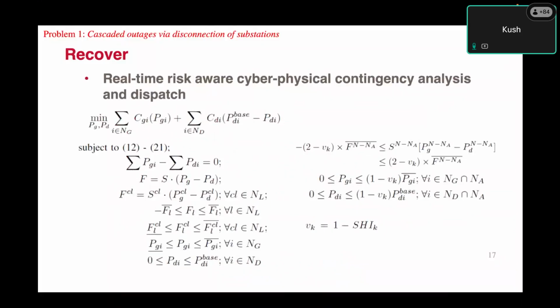So traditionally, we are using only physical contingency analysis. This physical contingency analysis says that if, say, one transmission line is out because of a fault or something, is the system good enough to handle all the load or not? But now, if we use this substation health index, we can incorporate that to screen the cyber physical contingencies as well, along with the physical contingencies.